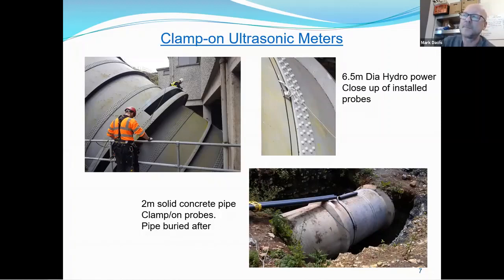Those probes, dimension-wise, are about 2 centimeters square, so that gives you an idea of the size. The picture on the bottom shows a buried solid concrete water pipe. This pipe is full. It's used for supplying water to a very large city. We are measuring that flow without breaking into the pipe, using clamp-on ultrasonic probes. After the probes were installed, the entire pipe was buried again.